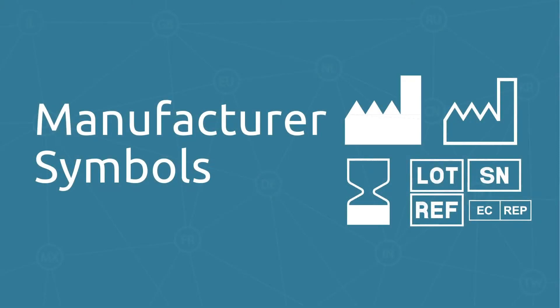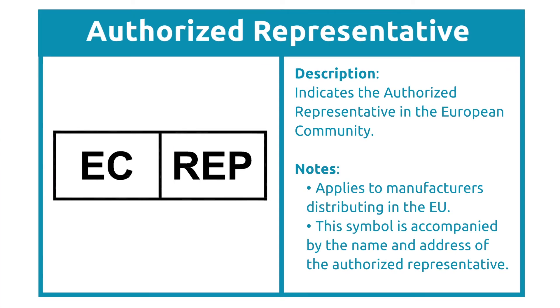Manufacturing symbols represent the manufacturing information about the product — things such as when and where it was made, as well as product identification data, fall into this category. The manufacturer symbol is a factory silhouette used in the EU, and includes the name and address of the manufacturer next to it. Another symbol used in the EU is the Authorized Representative, also known as the EC Rep — the name and address of the authorized representative are placed next to the symbol. The Date of Manufacture symbol looks similar to the manufacturer one, except it's hollow. This states the date the product was manufactured and must be expressed in a 4-2-2 date format: 4 digits for the year, 2 digits for the month, and 2 digits for the day.